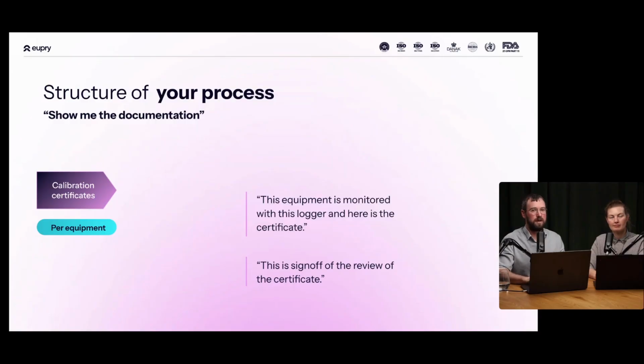There's another question about which kind of documents an auditor would like to see, and that can depend on the type of auditor. Some auditors want to see even down to the raw data, and can dig down a rabbit hole, going all the way to looking at the training received by the calibrator for a certain calibration certificate. But you could also choose to stay from the top and look at the procedure first, to see, okay, this is what you say you're doing, and this aligns with the GxP requirements we're auditing into. Then you can move down, as we pictured here, from the process all the way down to the specific documentation.